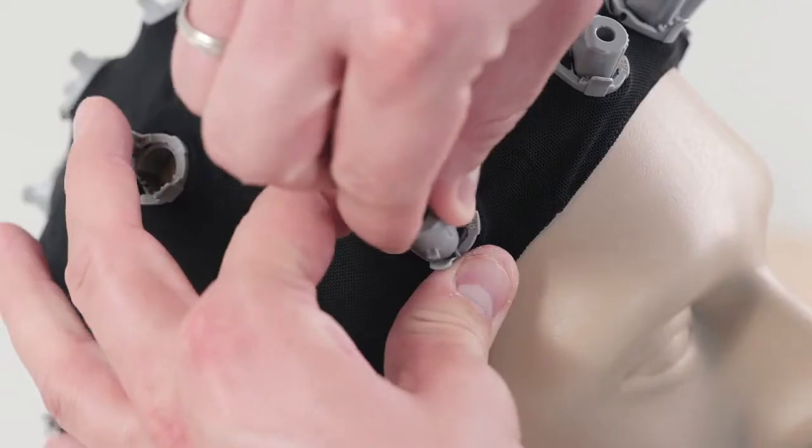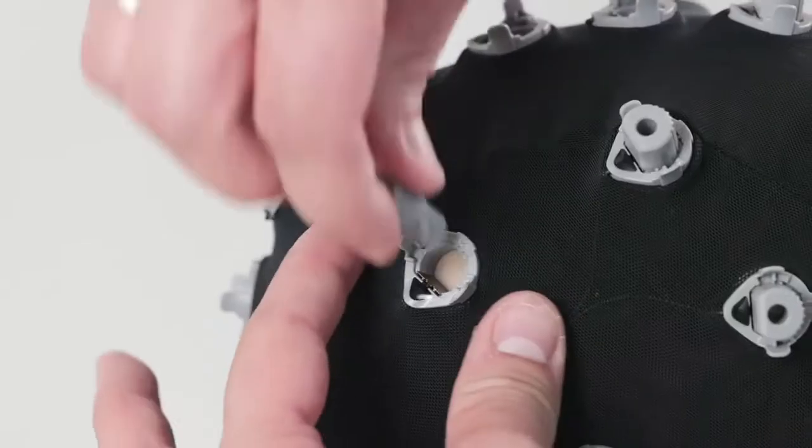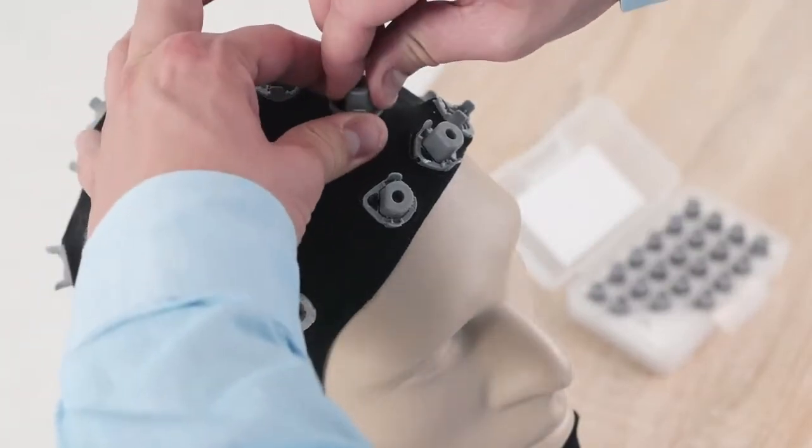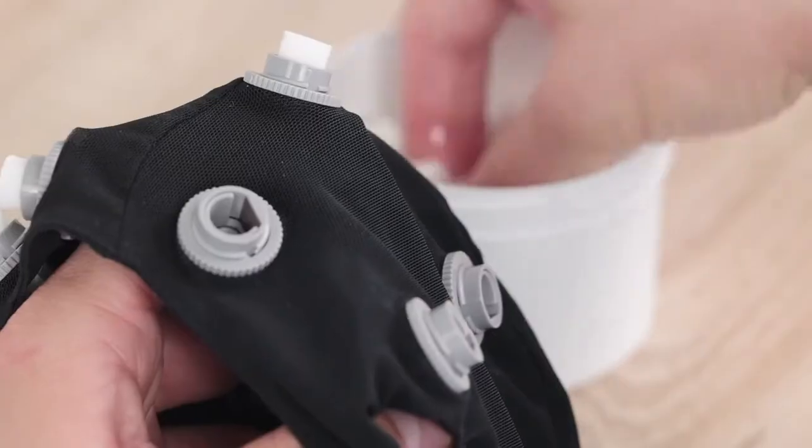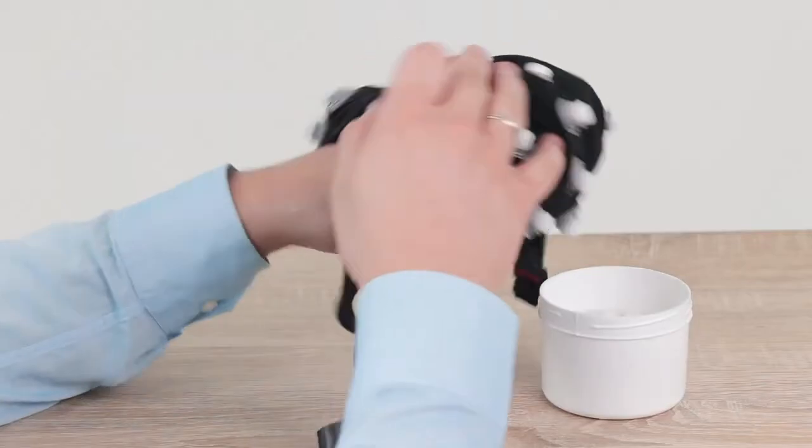Insert the sponge holder into the electrode base. Screw the sponge holder clockwise. A click sound indicates that the holder has been properly placed in the electrode base. Take the sponge from the wetting container and gently squeeze out any extra saline solution. Place the sponge in the holder.